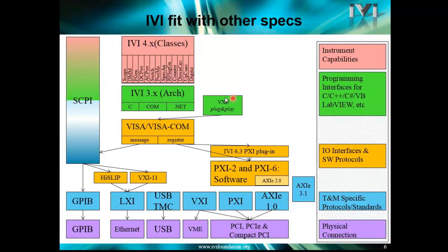The next layer that's really described here, and you can see it's kind of a natural built-in part of SCPI, is the layer that provides the programming interfaces to the instrument. So things like C and C++ and C#, Visual Basic, LabVIEW, all have different needs for a software instrument driver to work on the system.